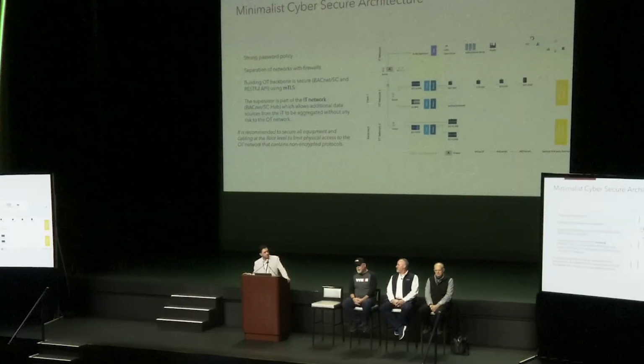I think you're going to see tools evolve too, Mike, like Qualys or Nessus, things that today are threat assessment scan software. They're going to expand the umbrella of what they're looking at probably. And they're going to start trying to validate whether our certificates expired or who they were signed by or things like that. Not today, it hasn't grown to that, but I would foresee people expanding what they look for as far as vulnerabilities. Is there BACnet IP UDP traffic still on the network after we implemented SC, and do other validation tests, I would suspect.